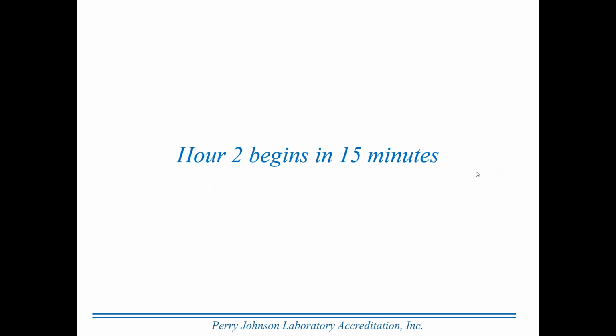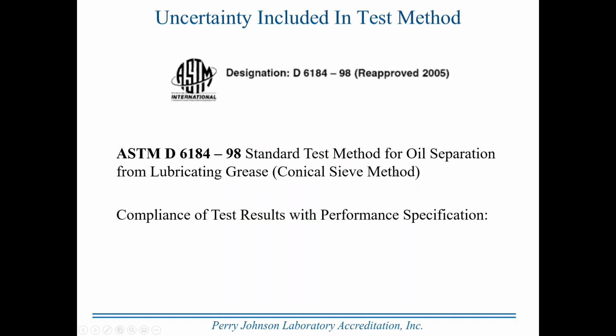Okay, that's close enough on the 15 minutes, so let's get back to our presentation. We want to talk first about measurement uncertainty included in a test method. This is, again, one of the things that's unique about testing: oftentimes the nature of the test is such that acceptance criteria have been developed for the test, and the manner in which the acceptance criteria was developed included the uncertainty resulting from the test results obtained in developing the method. Typically, the method would have involved a large number of laboratories performing a large number of tests, so a lot of data. And when you're doing statistical analysis, if you have 30 values, that's considered a statistically significant sample. And you may hear that again later in the presentation.